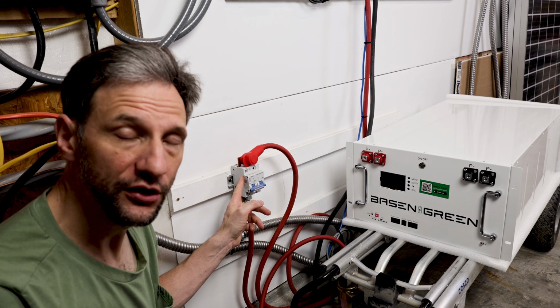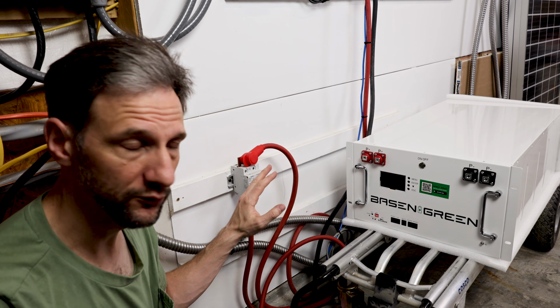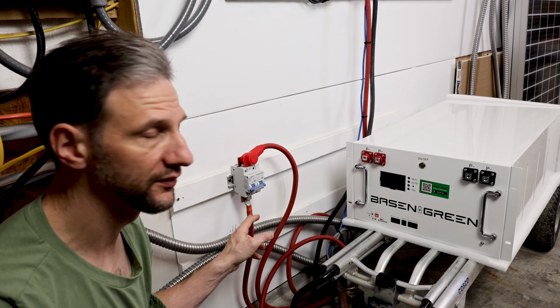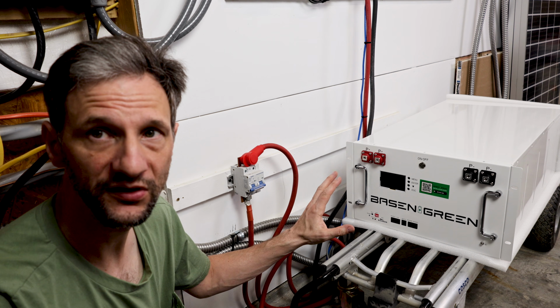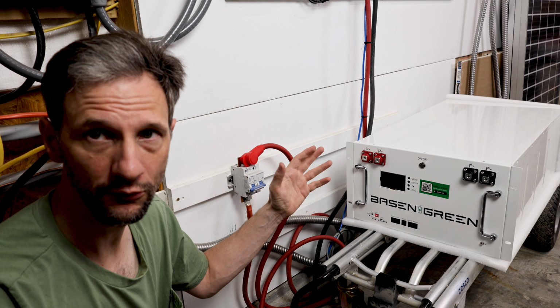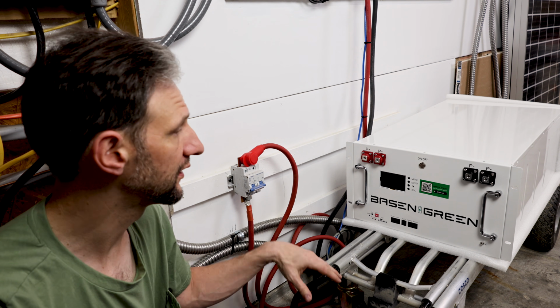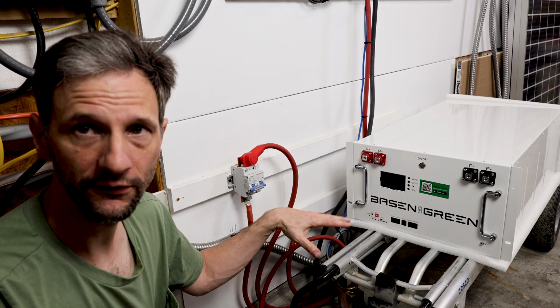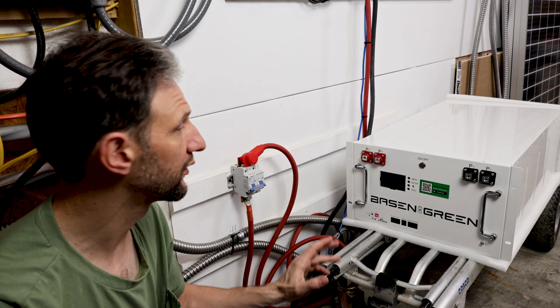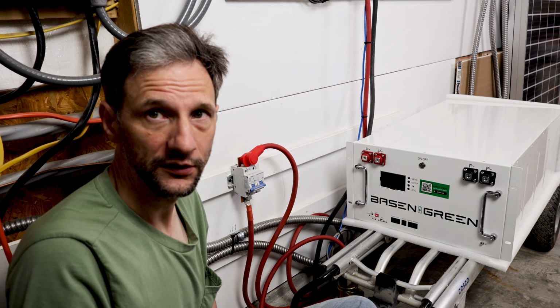This breaker should be in its own box with a little cover on it so you can't have access to these exposed terminals. And I would be standing the battery up against the wall and chaining it to the wall in case of an earthquake or something, with spacers and 2x4s underneath to hold it up off the floor. But we're just running tests here, so I'm not too worried about that.